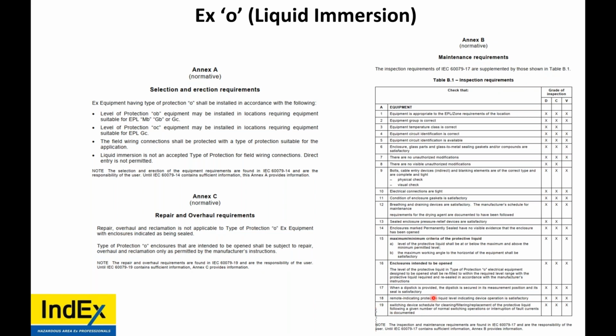So while you will have an inspection sheet as per -17 for the other EX protection techniques on the transformer, because as we showed, it's not just by itself EXO, there will be D and other protection techniques. These questions are specifically for O, asking the minimum and maximum criteria of protective liquid. How much liquid is in it? Is it too much? Is it too little? If it's intended for opening, you follow that. Dipsticks, remote indication devices, switching devices, gaskets. So this is specific for EXO.